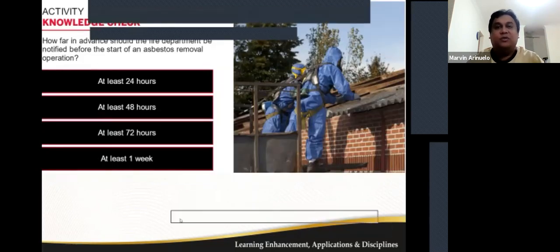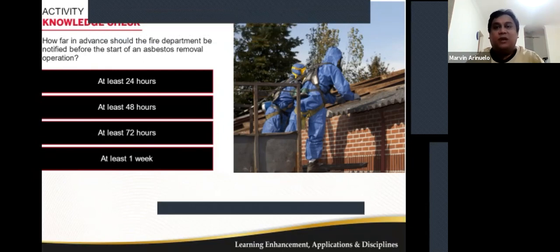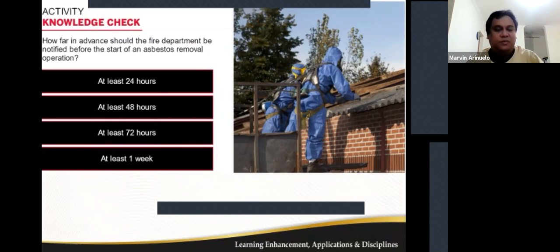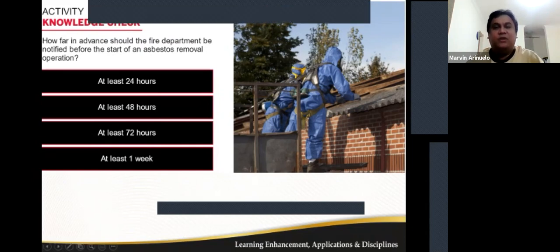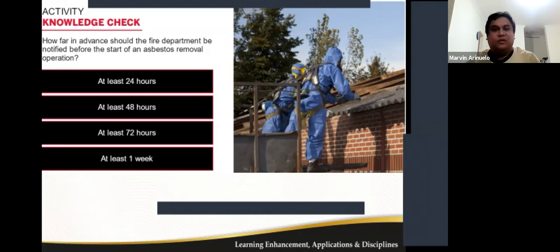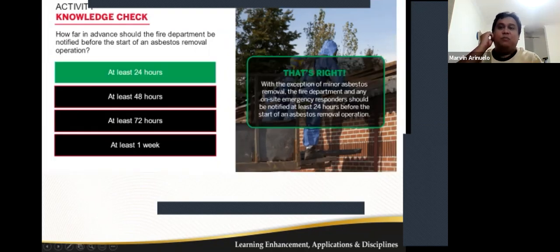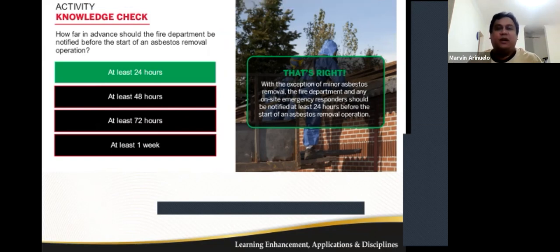I gave you extra resource material, a relevant section of the fire protection handbook, earlier. So how far in advance should the fire department be notified before the start of an asbestos removal operation? Any idea? I've shared those reading materials with you earlier, so if you read that, you will know the right answer. The answer is 24 hours at least. With the exception of minor asbestos removal, the fire department and any on-site emergency responder should be notified at least 24 hours before the start of an asbestos removal operation.